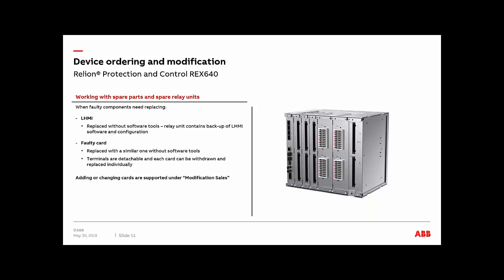If you have a faulty card, you can replace it with a similar one. No need for software tools. You just have to follow the procedure for the exchange and plug in your new card or module or communication module or anything that's on the back of the relay. Everything is modular and it can be replaced.